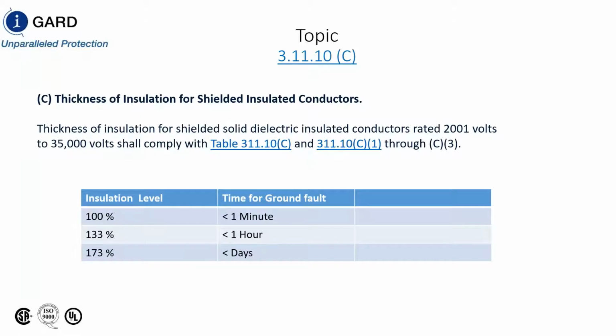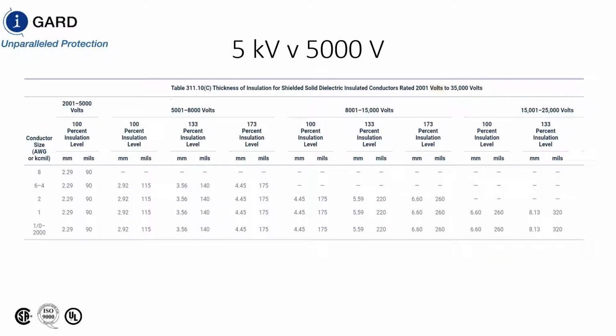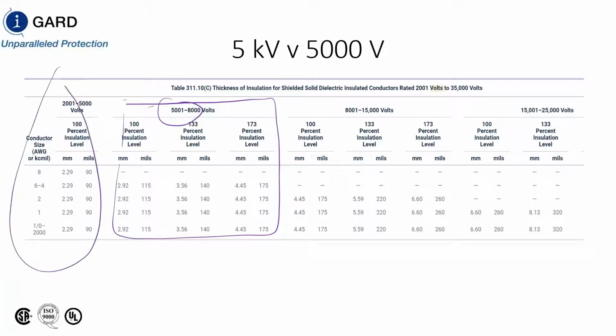So the reason why 5 kV and 5,000 volts is such a delineation is because if you look at table 311.10c, and 311.10c1 through C3, basically says that for a ground fault on your system that's less than 1 minute, you need 100% rated cable. For less than 1 hour, you need 133% rated insulation. And for a fault that's going to be on your system for greater than 1 hour, you need 173% rated cable. But if you look at the table, the delineation is not 5 kV, it's 5,001 volts. So for 5,001 volts and above, you have the 100, the 133, and the 173% rated cable. For anything less than 5,001 volts, there is no separation between 100, 133, and 173% rated insulation.